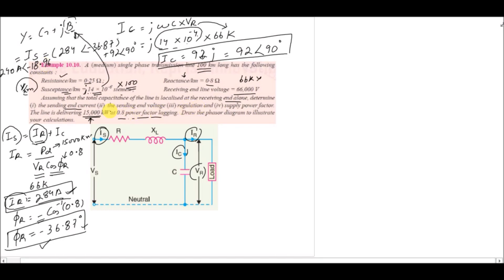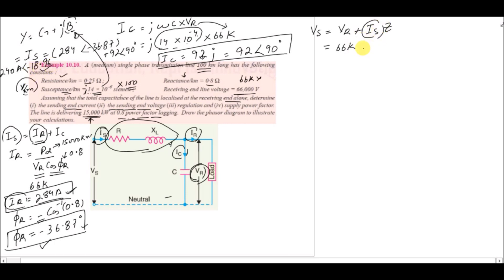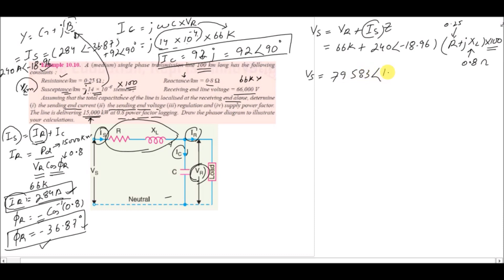For the sending end voltage: VS = VR + IS × Z. VR = 66 kV, IS = 240∠−18.96°, and impedance Z = (R + j·XL) × 100, where resistance is 0.25 Ω/km and reactance is 0.8 Ω/km. Multiplying by 100 km gives the total impedance. The result is VS = 79,583 V∠11.50°.